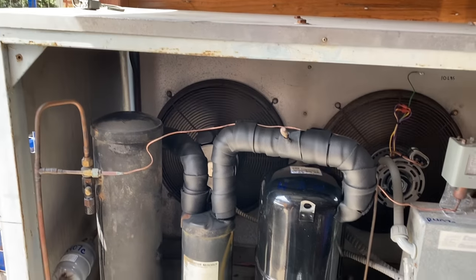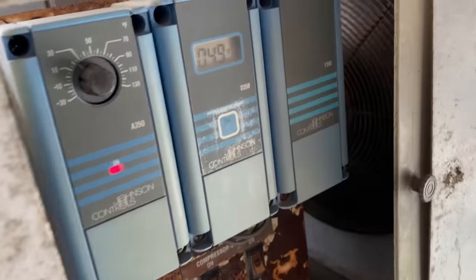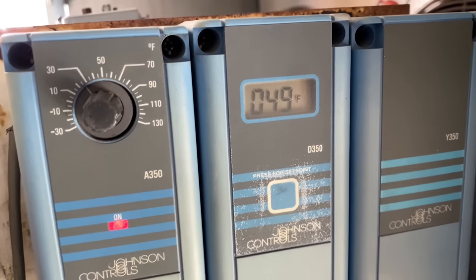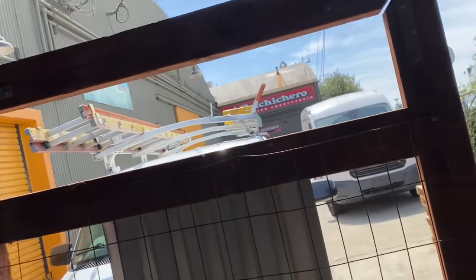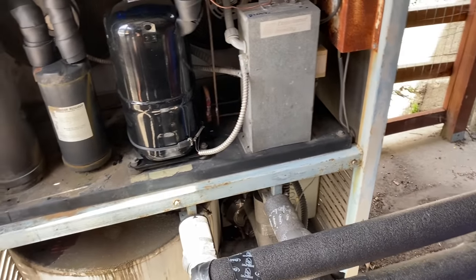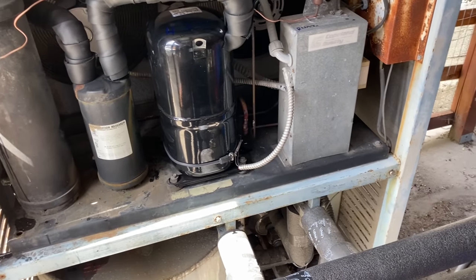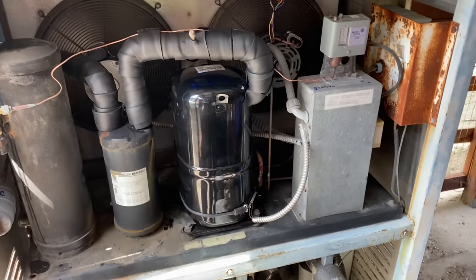I'm gonna make some paperwork, and then we'll check back on the temperature. All right, so we're heading in the right direction. Man, it's too bad I couldn't get in there to show you guys everything. It's all locked up, but all the tanks are hot. It's got a huge, huge load to go. So I checked the compressor with the Copeland app. Everything's within specs.